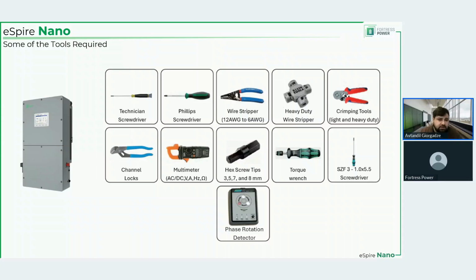Here, phase rotation matters. L1 should go to L1, L2 should go to L2, L3 should go to L3. So while you're connecting those AC cables to the inverter, you must check phase rotation to make sure that the rotation is correct and the inverter is not going to go crazy and throw errors when you turn on the AC input to the unit, right? So a phase rotation detector is a must when working on these three-phase units.